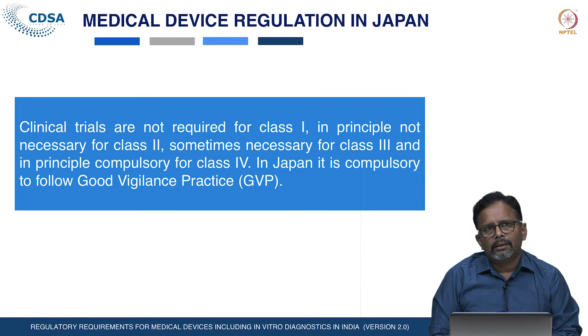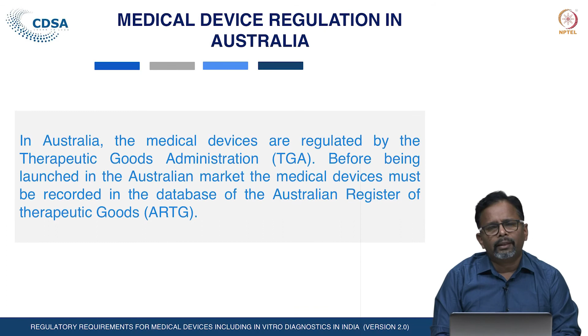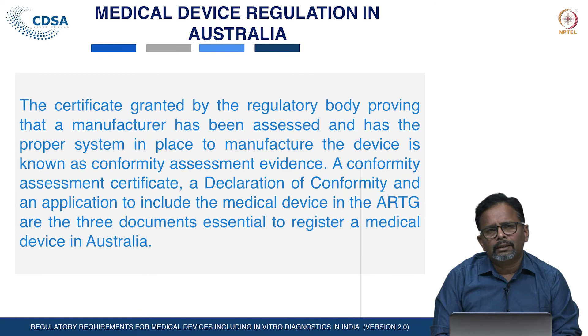For in vitro diagnostics in Australia, there is a different classification system. A manufacturer has to prove that the devices and the manufacturing process used to make the device adhere to the requirements of the therapeutic goods legislation and conformity assessment. The certificate granted by the regulatory body, showing that the manufacturer has been assessed and has the proper system in place to manufacture the devices, is known as the conformity assessment evidence. The conformity assessment certificate, the declaration of conformity, and an application to include the medical devices in ARTG are the 3 documents essential to register medical devices in Australia.